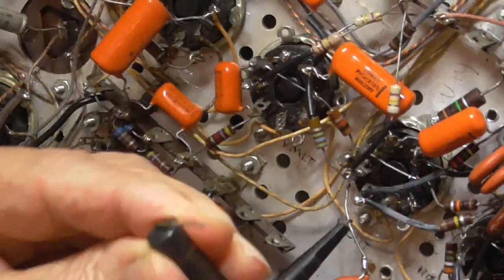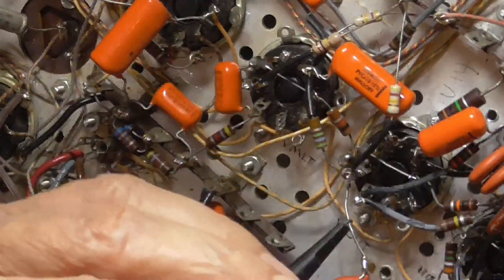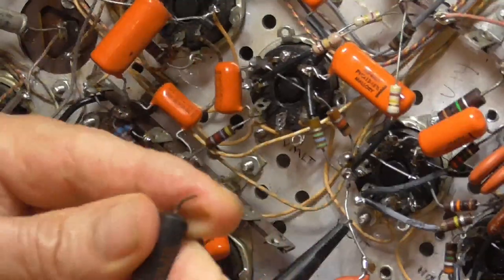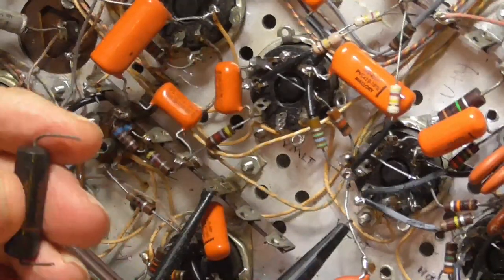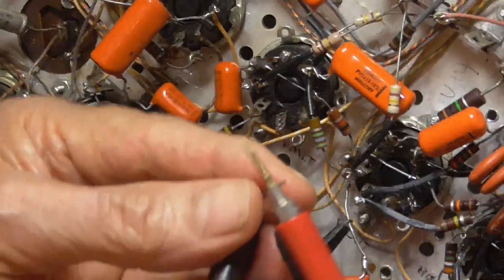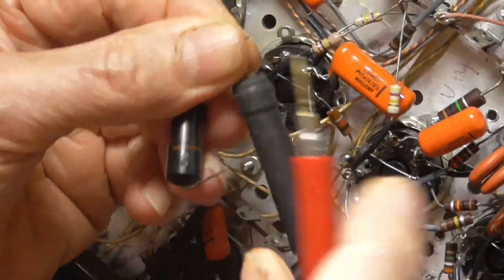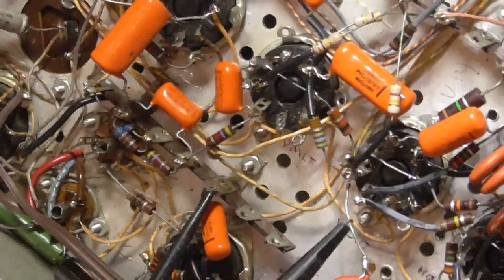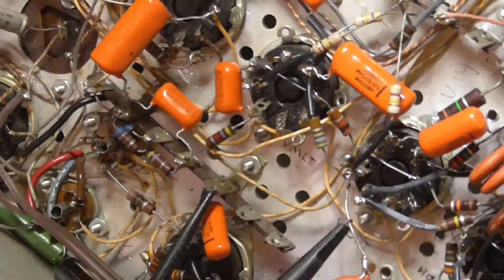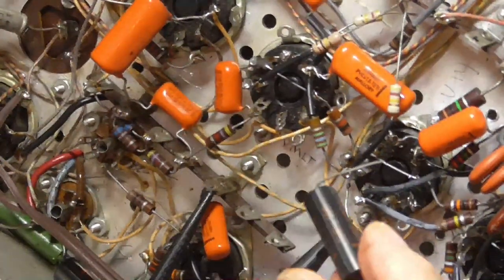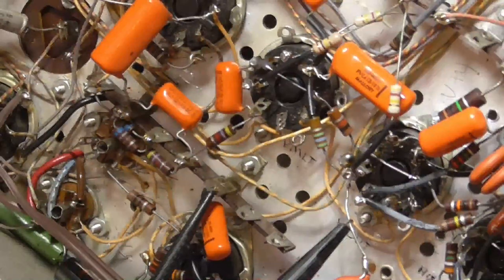It's not leaking. If it leaks, it'll make the frequency go higher. So since we're lower, we clearly don't have leakage. If I look up here with a meter, it's way over 20 megs. Okay, I'm going to start up the capacitor checker. Instead of 0.01, it's reading 0.012. So it's about 20% high. That doesn't account for the error.